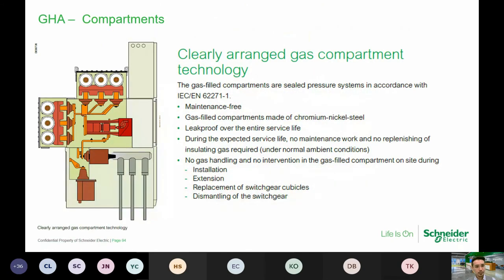Right, so what we've seen earlier is a single compartment, and this one just gives the overview of a double compartment GIS. So the double compartment has the LV compartment in here, and then there's a bus bar compartment that's separated itself, and then there'll also be a circuit breaker compartment, and also a cable entry compartment in here. Okay, so having all these in the SF6 gas is again maintenance free. It's a gas filled compartment made of chromium nickel steel. All right, so it's leak proof for the entire service life.